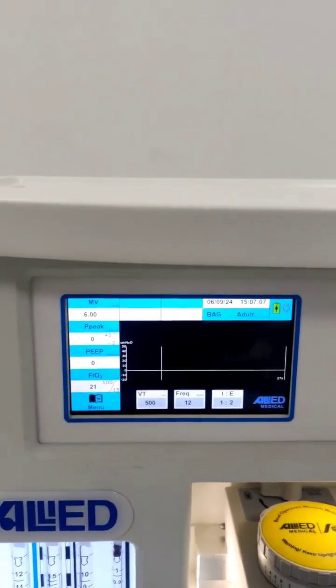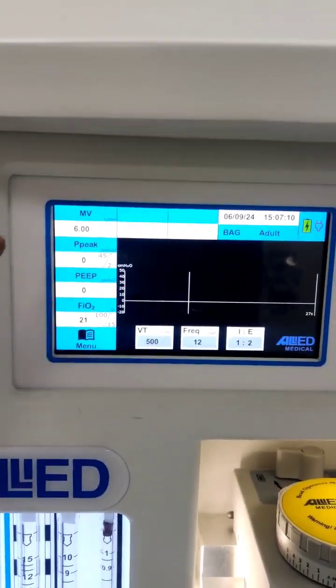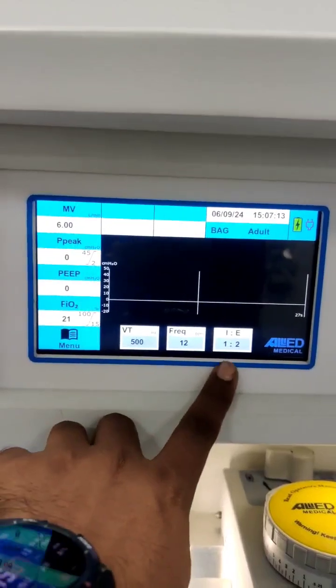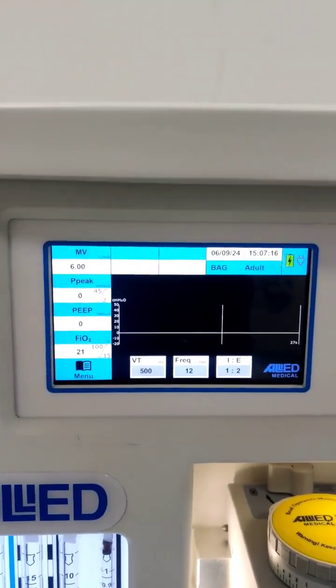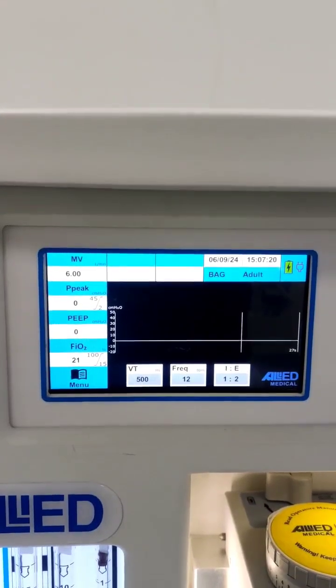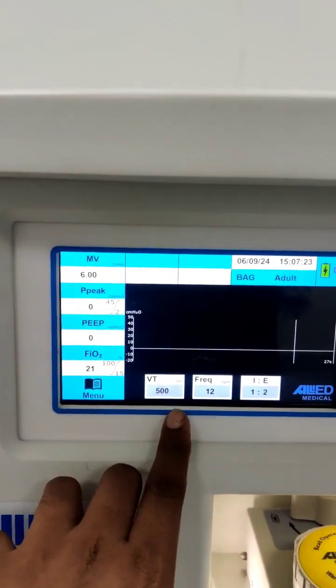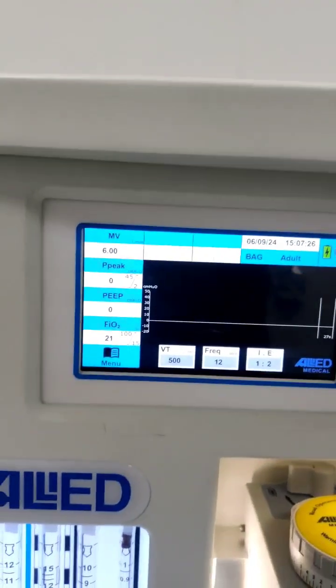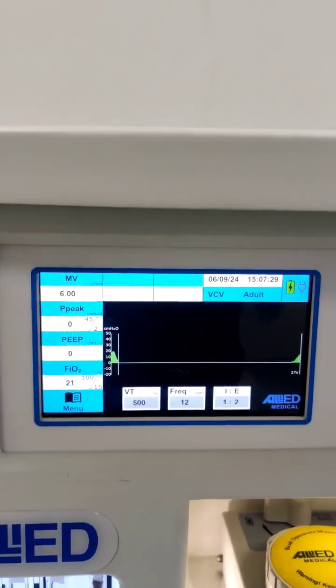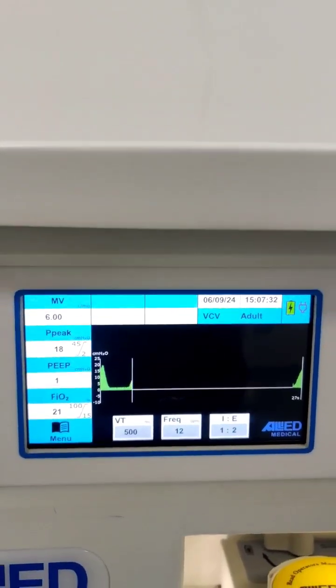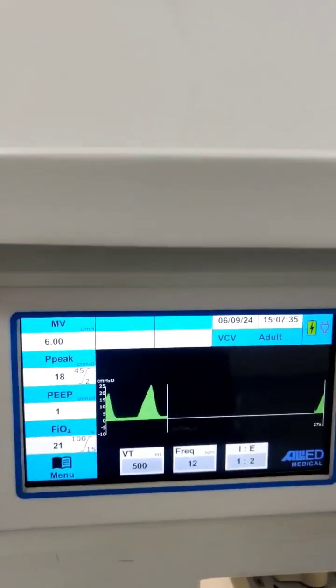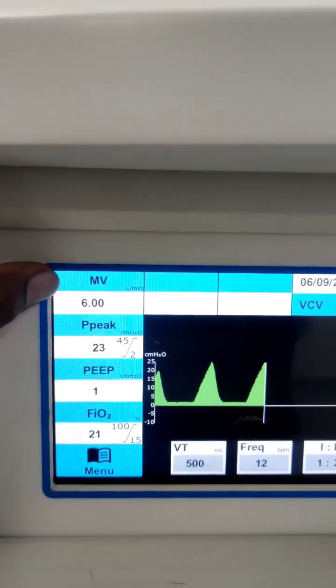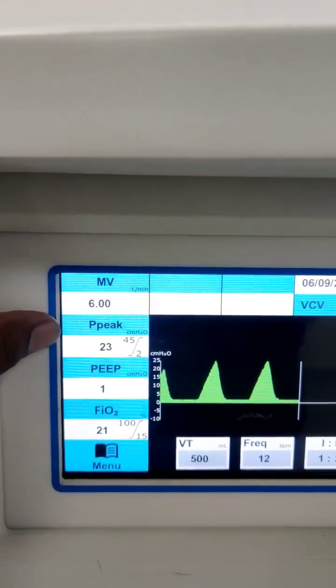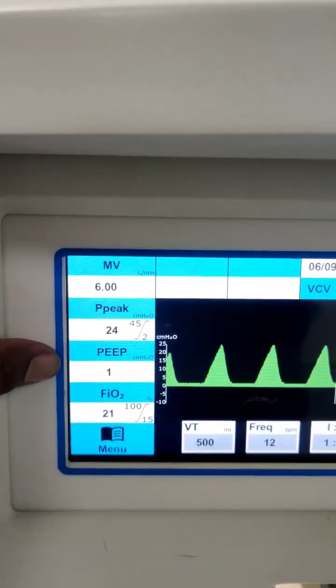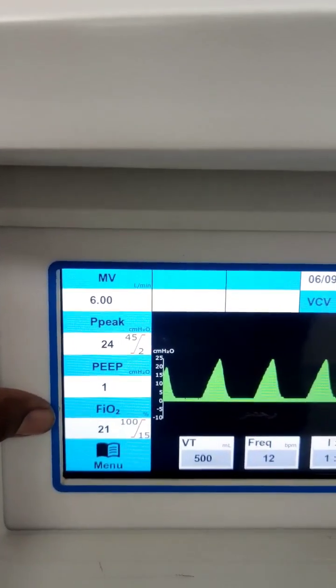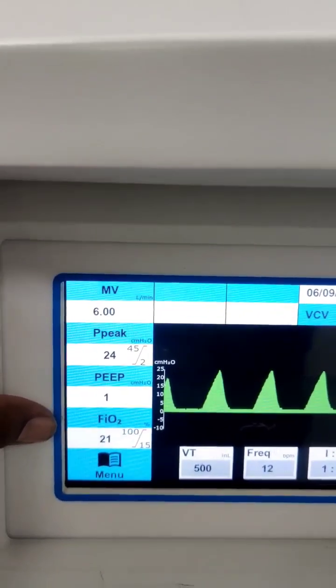This is how the interface will be shown on the screen. We are getting the monitored parameters on the left side, and these are the settable parameters. This machine operates only on a single mode of ventilation, that is volume control ventilation. You can set the tidal volume, the frequency, and the IE ratio. You will get a single waveform, the pressure versus time waveform, displayed over here. On the left side, as I mentioned, these are the monitored parameters, showing the minute ventilation, the minute volume, the peak pressure, the PEEP which is being generated in the patient lungs, then the FiO2 value which is being measured through the oxygen sensors, which I have already demonstrated in the video.